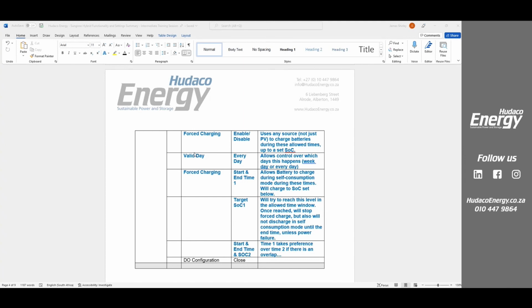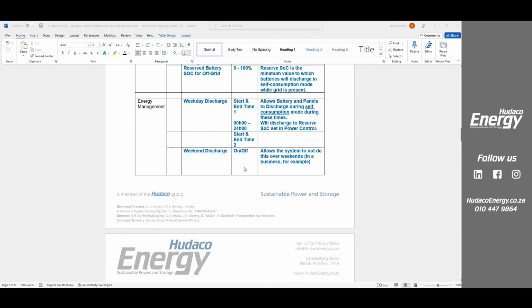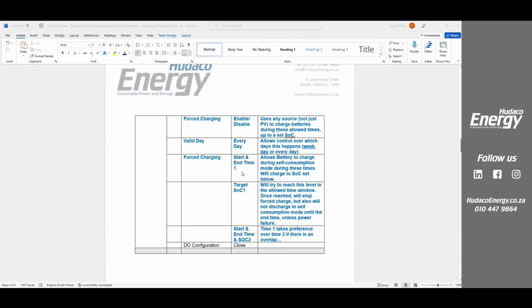Okay, what's really important to remember is your forced charge window, your time slot, this one, takes preference over your discharge time. So in other words, even if, let's say you've set forced charging till 6 o'clock at night, and you set it to 80%, and maybe it reached 80% at 4 o'clock in the afternoon, just from solar power, for example. The fact that you have forced charge set and active, even if it's at that level, you will not cycle your batteries until you're out of that block, because it's telling your inverter, make sure my batteries are at this level by this time.